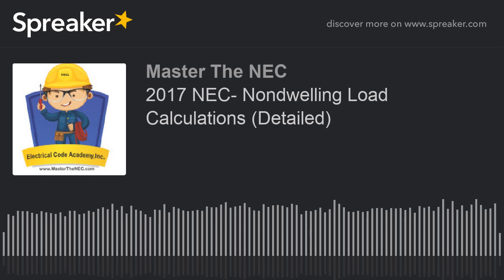And that's going to be the total of all your motor loads, okay, plus the additional 25% for that largest motor, okay? So again, in a simple way of saying that is add all your motor loads up, and find out which one's the largest, and then take that one and multiply that by 25% and add that value onto your motor load you just all added up, okay?